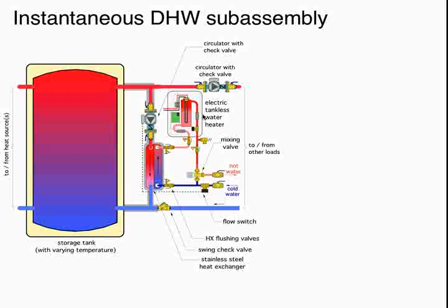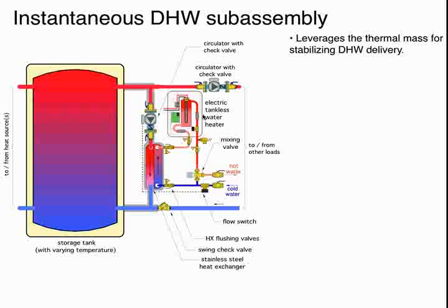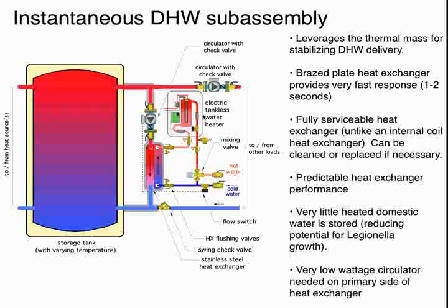It is important that this is thermostatically controlled, because a thermostatically controlled heater will add just the right amount of heat to bring that water from whatever preheat condition we supply it up to a set point. We won't overshoot. Okay? And there's a lot of advantages to this approach. Again, it leverages a single thermal mass. This can also provide space heating. Okay? Fast response time. We have everything outside the tank. We don't have internal coils that could potentially scale up or ultimately fail, in which case we have to replace the tank.